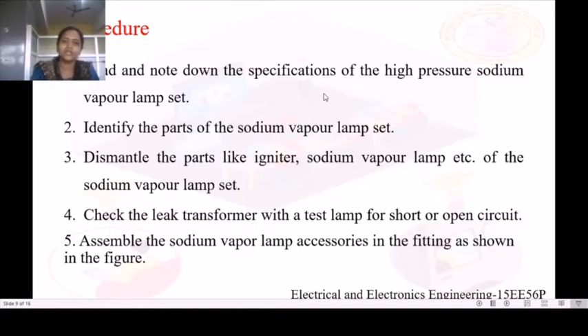Then we need to test all the parts of the sodium vapor lamp set for any short circuit, open circuit, or any ground fault using a series test lamp. After testing the parts, we need to reassemble the sodium vapor lamp set parts in the lamp set fixture as per the circuit diagram.